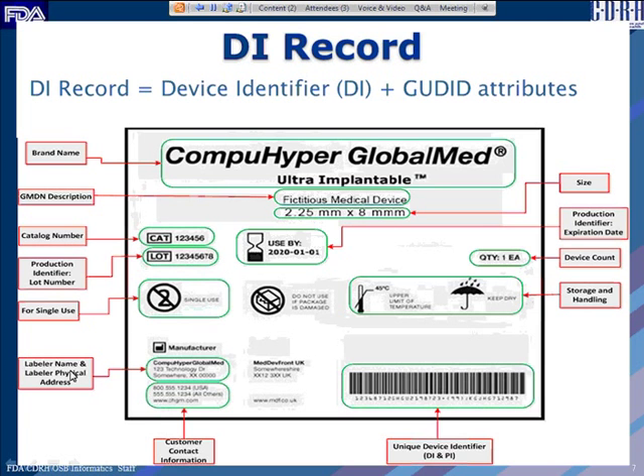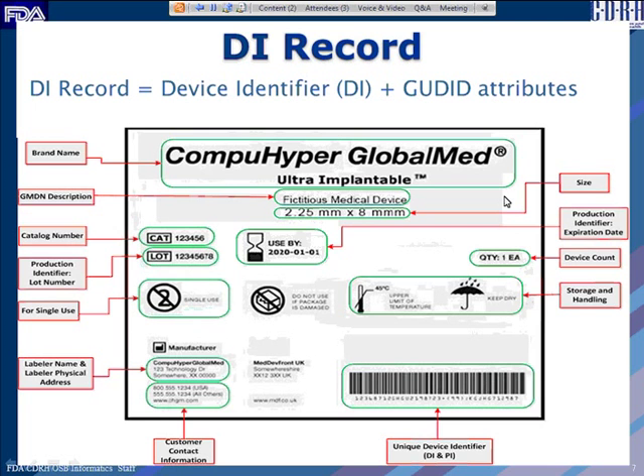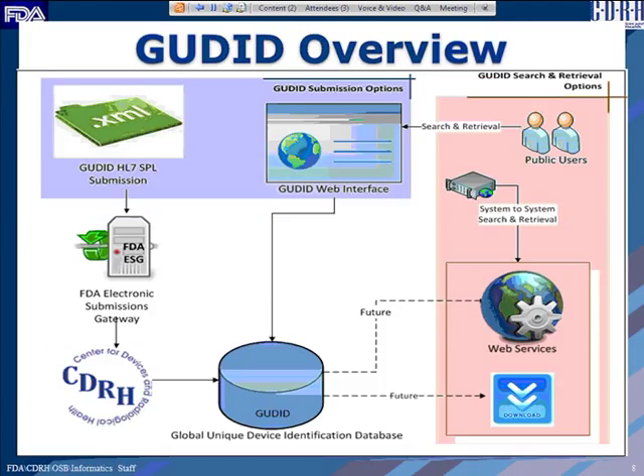Other DI record attributes include storage and handling, the count of the device — how many devices are within the package — expiration date, and size of the device. A good way to think about a DI record is it is a subset of what might be on the label or labeling of the device.